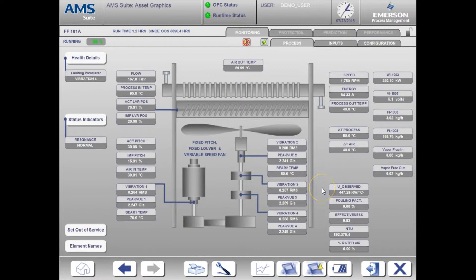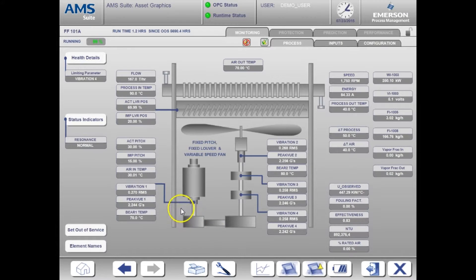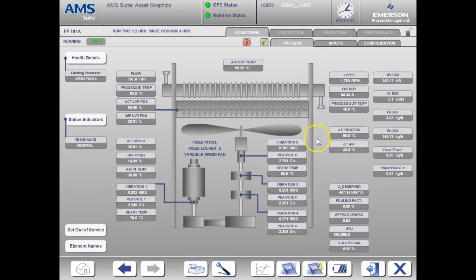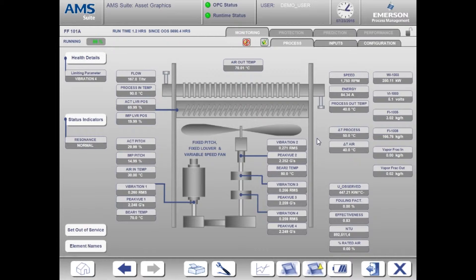This particular exchanger is a fixed louver, fixed pitch, variable speed fan. However, this could have easily been a variable pitch or a variable louver position fan. In those cases the application would use pitch or louver position in the same way as it uses speed.